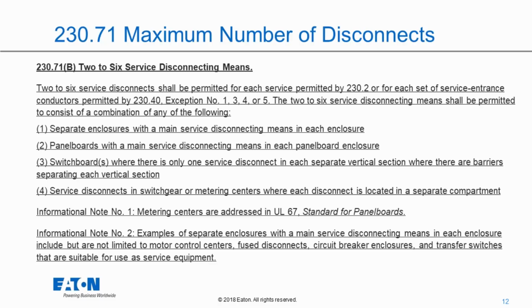The second one is a panel board with a main service disconnecting means in each panel board enclosure. So again, they're allowing you separate services, but they're making sure that you have separate enclosures for each of those service disconnects. A switchboard where there is only one service disconnect in each separate vertical section, where there are barriers separating each vertical section. And again, there might be some interpretation needed as to what barrier is sufficient for that.